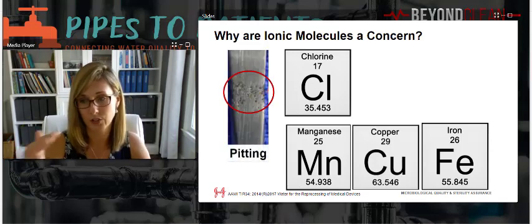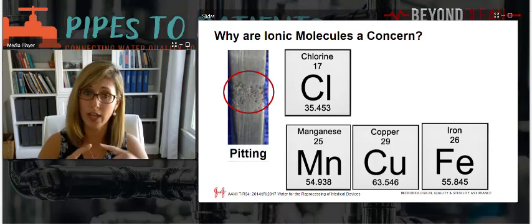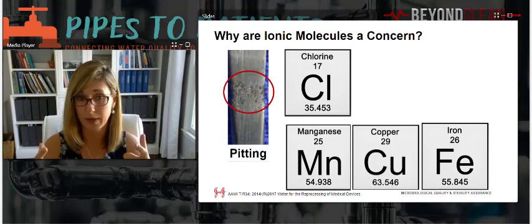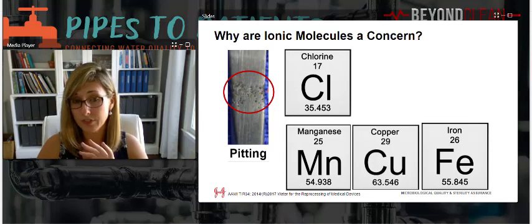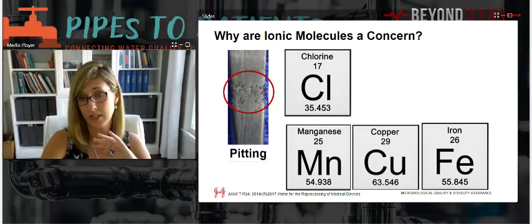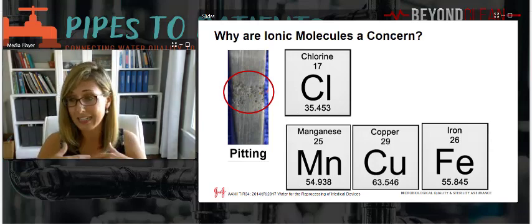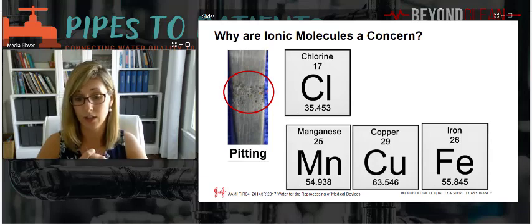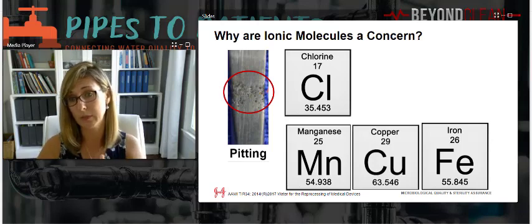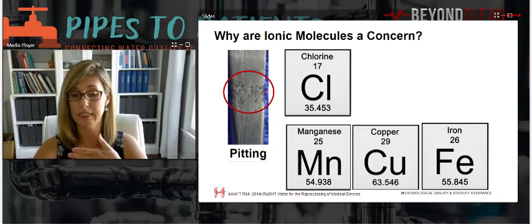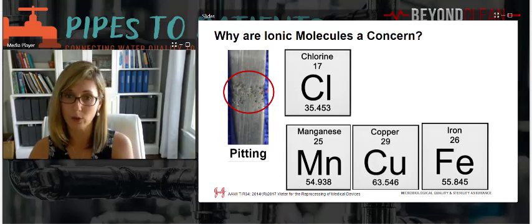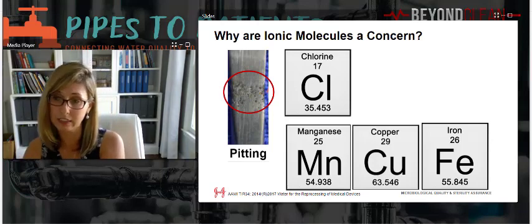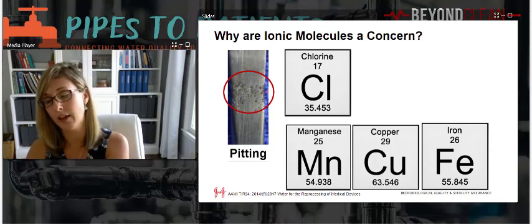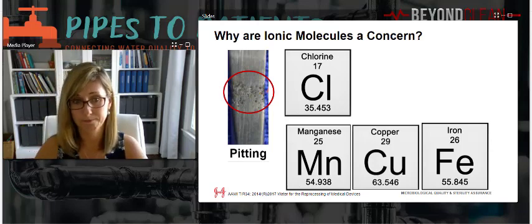That's where the surface characteristic of the device is altered and a rough surface becomes apparent, which means it's more difficult to clean. If you have soil depositing in those pits that aren't intended to be cleaned using the instructions for use, you have residual soil built up on a portion of the device that's now harboring soil, which means it's harboring food, which means microorganisms can grow, which means we can't clean and sterilize, which means we have a patient safety risk.